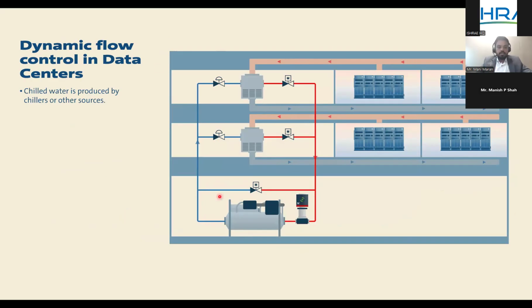So it's a simple SLD for the benefit of discussion. We have a chiller, which is a primary circuit, and a pump which is driving the flow into the chiller. The red line is the return from the load from the data hall, and then the water gets into the chiller, and then the supply water from the chiller gets into the data hall. It's a pretty basic design, and assume these are the loads.